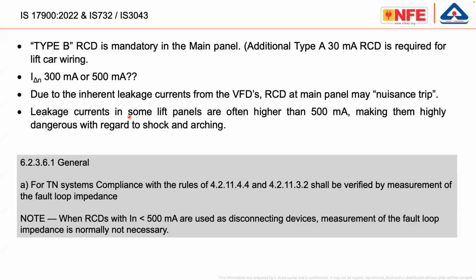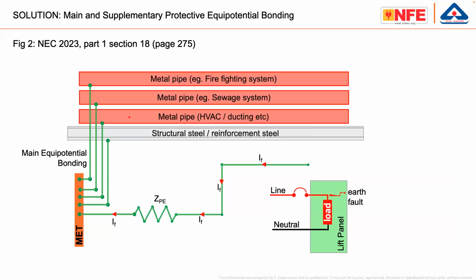That means if we continue with the current system, in case of any earth fault at the high voltage side of the electrical installation, the lift may fail. So what do we do? Straight away, you can go to the NEC Part 1, Section 18. Also, this is from IS 732, but we have made some drawings, some simplified pictures, to sensitize people.